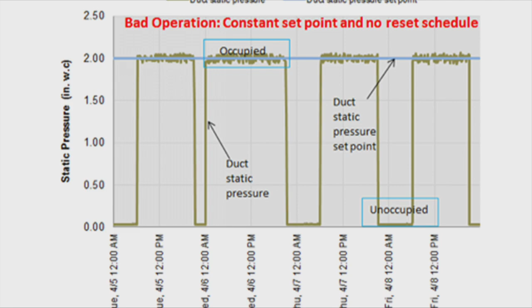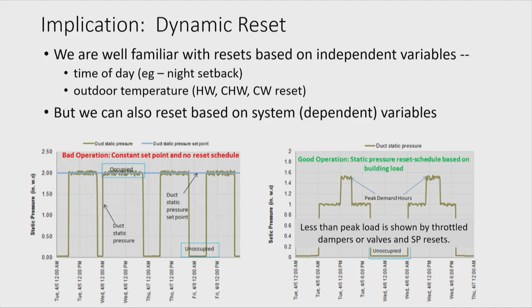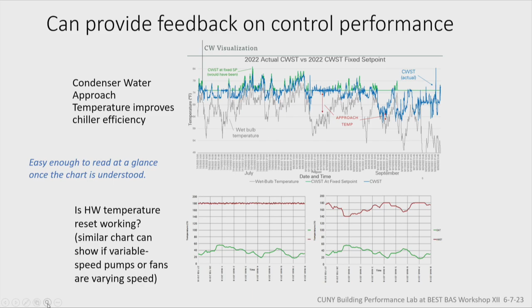Okay, good. So, we also use this kind of technique just as feedback to operators on their control performance. At the top, you can see a condenser water plot where the blue is the actual condenser water temperature. The gray is the outdoor wet bulb temperature. And you can see two different cases of approach temperature. In one case, the system condenser water was set to a lower temperature, getting to a close approach temperature. That, of course, unloads the chiller and improves its efficiency compared to a prior period where they maintained what had been a fixed set point.